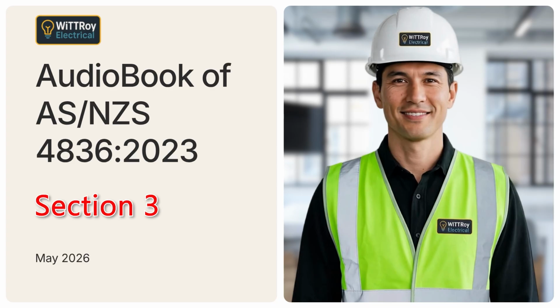The reason is simple. Automatic control devices can operate unexpectedly. Thermostats, switches, PLCs, and interface devices may cause circuit wiring to become energized again. When removing circuit connections, active conductors should be disconnected first. Then neutral conductors should be disconnected. Earth conductors should be disconnected last.